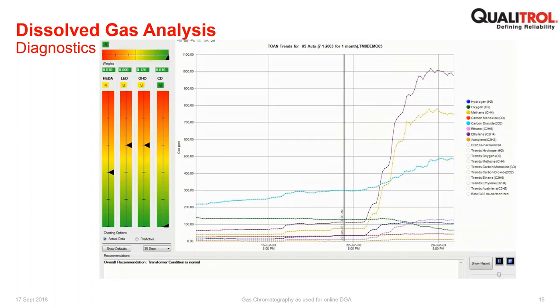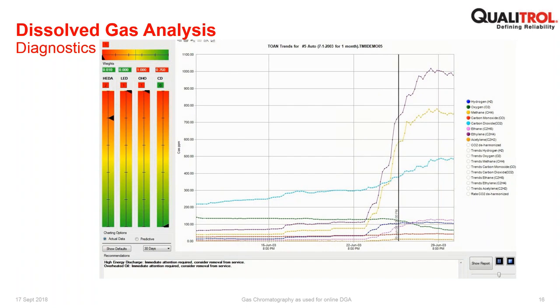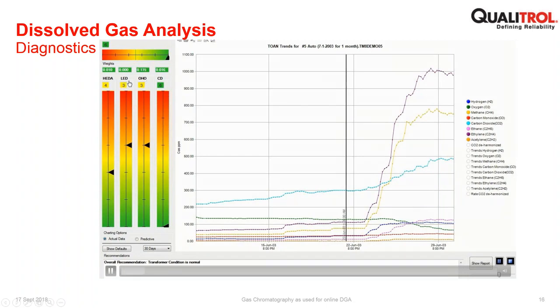There are other methods of looking at this. Qualitrol have a system licensed from a utility in the US called TOAN, and it's an artificial intelligence type system. And what it does is it looks at a library of failures, many hundred transformer failures, and using artificial neural networks, it will map the data coming from your transformer or from the transformer under test with this library of transformer failures and autopsies, and it will give a live indication of the presence or absence of a fault and the severity of that fault. And shown here, it's just scrolling through some data taken from a Serveron TM8, and it's showing a severe fault, the nature of the fault being overheated oil and low energy discharge as you scroll through it.